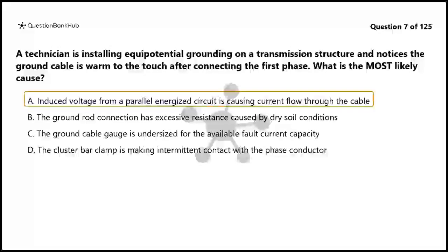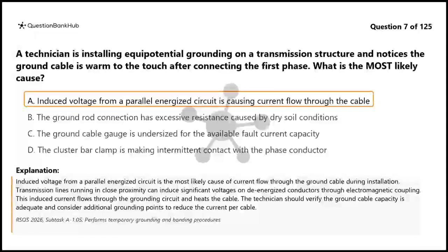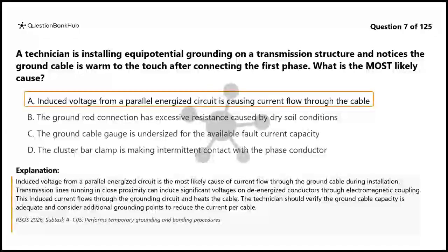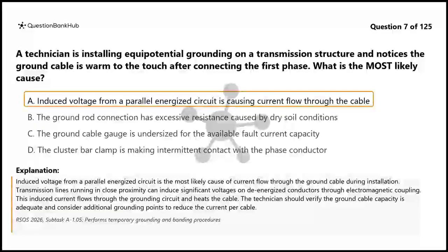The correct answer is A. Induced voltage from a parallel energized circuit is the most likely cause of current flow through the ground cable during installation. Transmission lines running in close proximity can induce significant voltages on de-energized conductors through electromagnetic coupling. This induced current flows through the grounding circuit and heats the cable. The technician should verify the ground cable capacity is adequate and consider additional grounding points to reduce the current per cable.